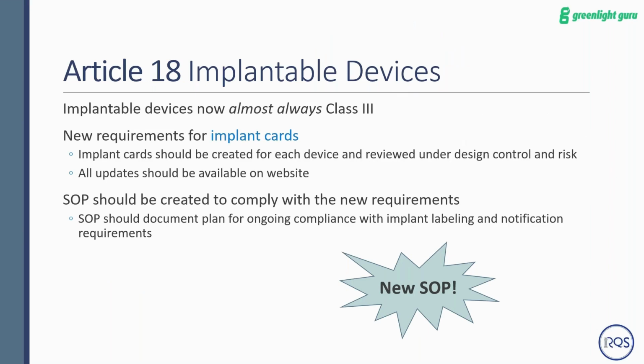All right, so for companies that are working with implantable devices, previously there were some changes, including MDR around classification. Now pretty much all implantables are class 3 at this point. With that, you'll have to have an implant card for each device that is implanted in a patient. These should be created and reviewed under design control and risk to make sure they have all the information, and all updates to this implant card should be available on the website as well as EUDAMED. This is going to be a new SOP if you are making implantable devices. Make sure that you have reviewed this section in detail and that you are complying with this in your procedures.